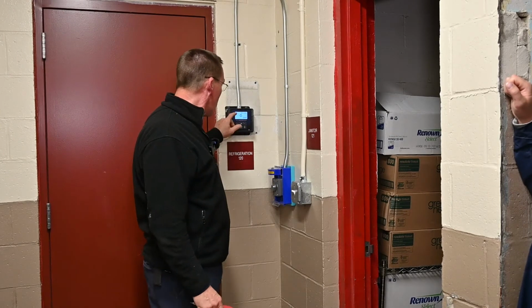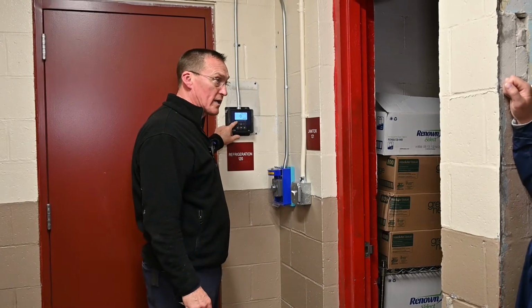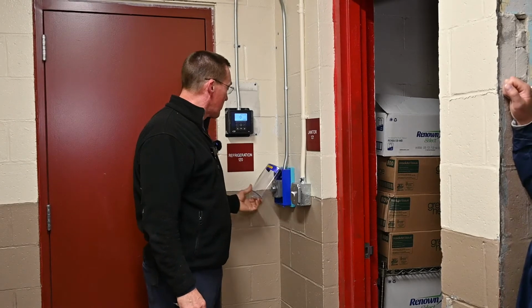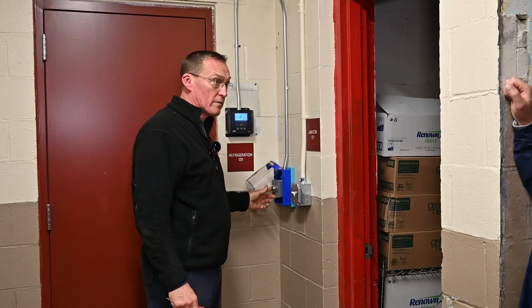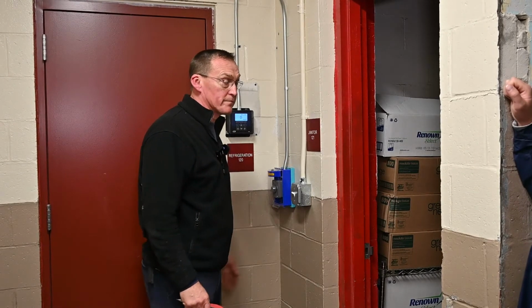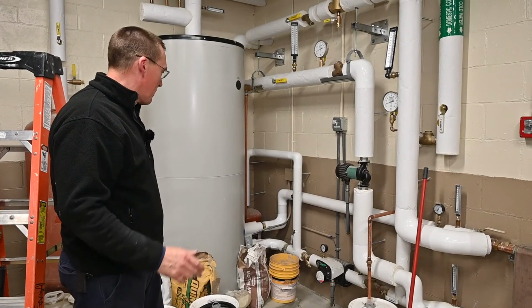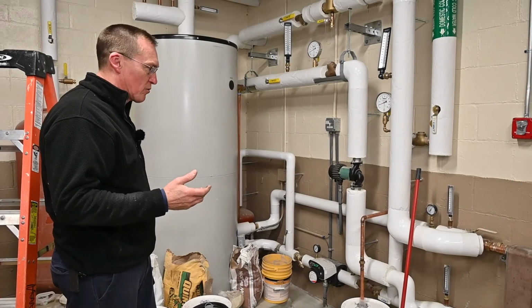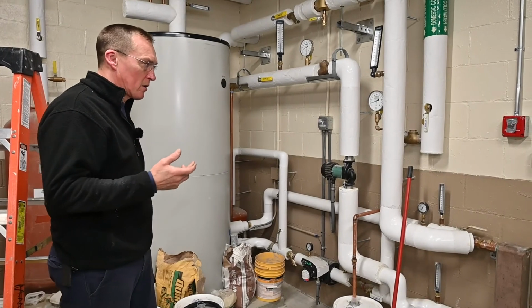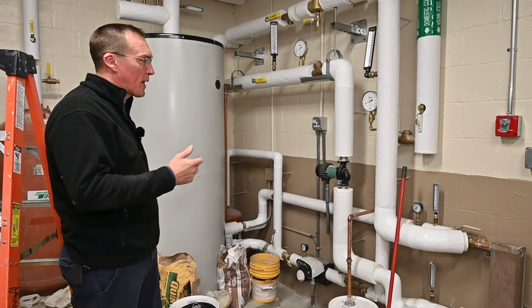Alarm's going to go off. Until this clears all the way down, you've got to get below 100. The only way you're going to shut it off is this blue button, okay? It's a latching relay, all right? Okay, so part of what Matt discussed with you guys was hot water recovery off our basically 100-degree warm glycol loop.